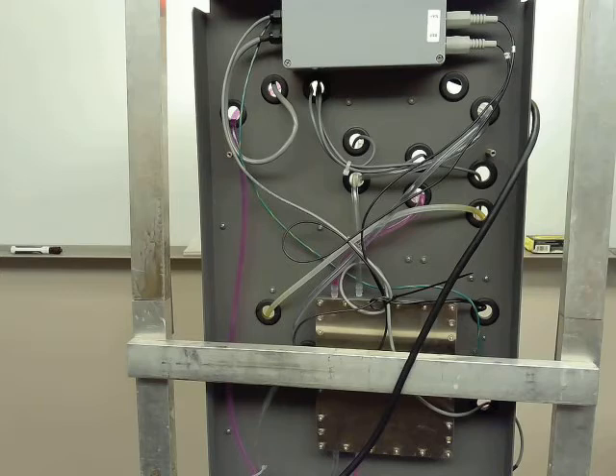electrodes. And I want to mention too that as part of the spare parts that you guys ordered and will be stocking in the warehouse, there is what we call a sodium spare parts kit that you have purchased. That kit has every fitting that goes on the analyzer, and also has a thermistor and a solenoid valve, and each one of those compartments is labeled individually. In the event that you use or consume all those items, you can just reorder that specific part. But keep in mind that if you get a broken fitting or a failed solenoid valve, you don't really have to panic, because you have that kit, and you'll be able to pull the necessary parts out of it to keep the analyzer operational, and then just reorder whatever component it might be, as you see fit.